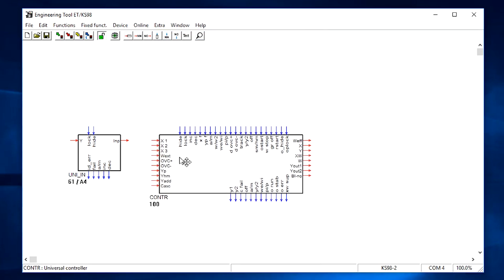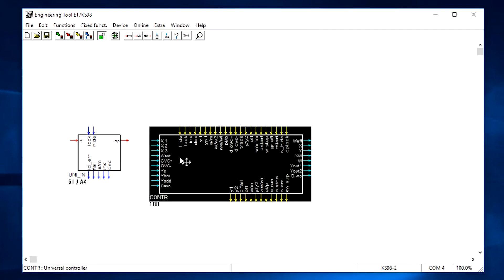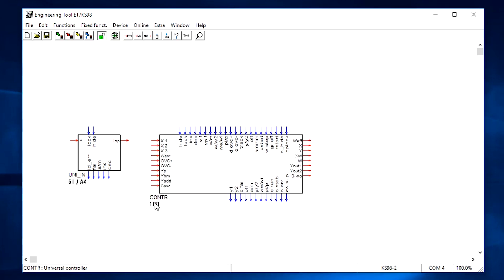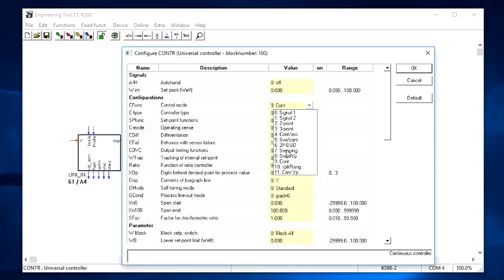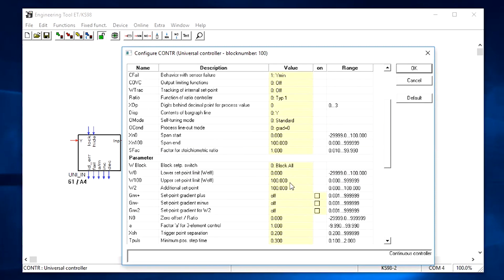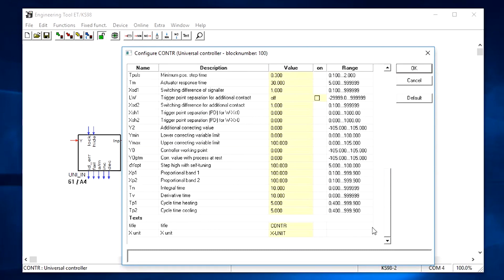It is a very flexible function block with everything you would need from the most sophisticated DIN controller. For a typical control function you simply need to drag and connect the first measurement input. Double click to open properties and set the control mode to continuous control. Set the control range from 0 to 1000 and the screen displayed to Fahrenheit.